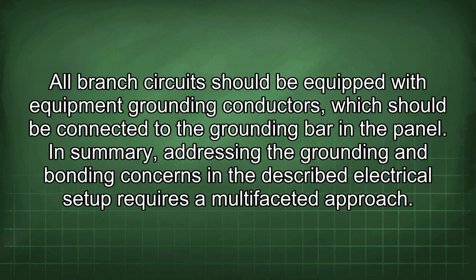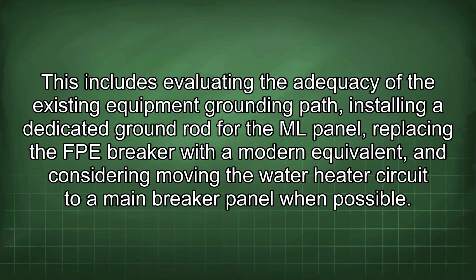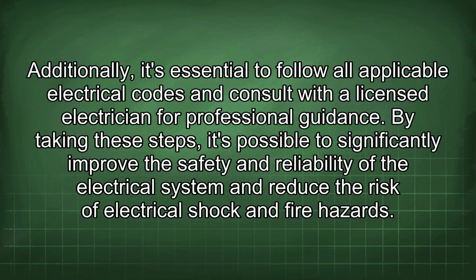All branch circuits should be equipped with equipment grounding conductors, which should be connected to the grounding bar in the panel. In summary, addressing the grounding and bonding concerns in the described electrical setup requires a multifaceted approach. This includes evaluating the adequacy of the existing equipment grounding path, installing a dedicated ground rod for the main panel, replacing the FPE breaker with a modern equivalent, and considering moving the water heater circuit to a main breaker panel when possible. Additionally, it's essential to follow all applicable electrical codes and consult with a licensed electrician for professional guidance.